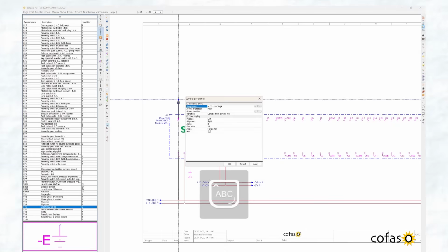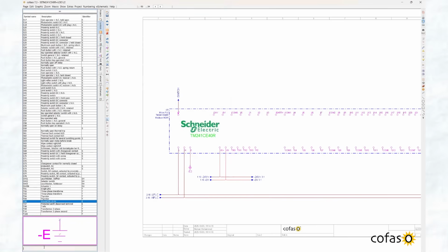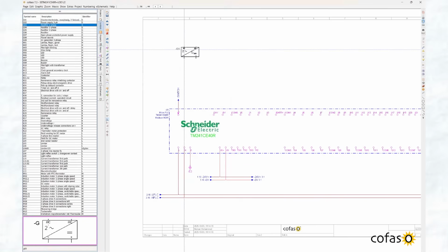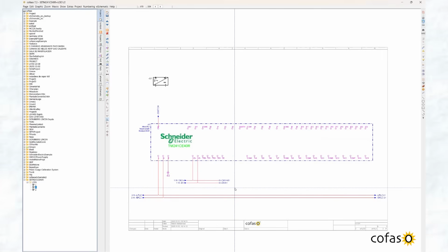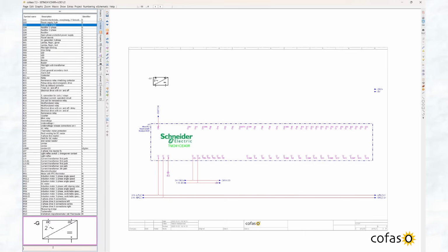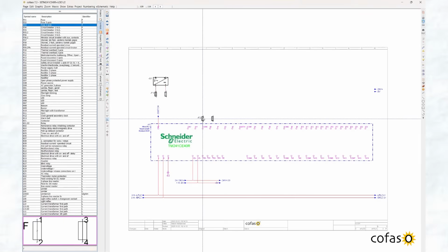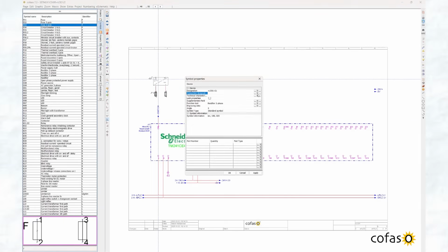I will simply put it here. Let's name it switch. It's an Ethernet communication switch. Click OK. Now in the symbol library, find G03 and put it here. I will get these two and put it here. Let's see the symbol library. Press F, grab fuse two pole, this one. Give some details. It's going to be 220V-24VDC and 6 ampere or 6A. Click OK and then apply.